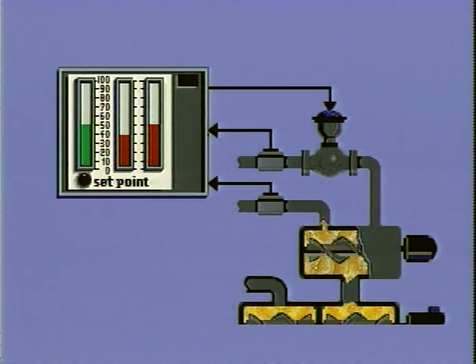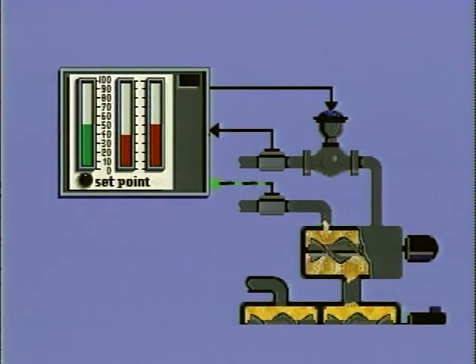In effect, he is trying to maintain the proper ratio of hot to cold water. A ratio control system accomplishes a similar adjustment automatically by using two sensors, a ratio controller and one valve. A sensor in the wild stream transmits a signal proportional to the flow rate to the ratio controller. The flow rate in the controlled stream is compared to the flow rate of the wild stream, and the ratio controller maintains the controlled flow rate to give the desired ratio for the mixture. This desired ratio is determined by adjusting the set point on the ratio controller. A high ratio means that the difference in the flow rates is great. A low ratio means that the difference is smaller.